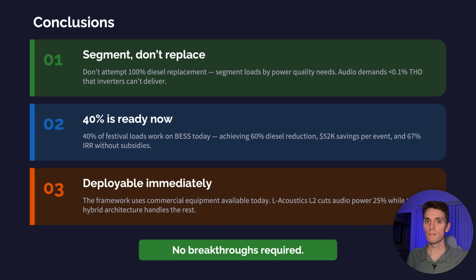3 takeaways. First, segment, don't replace. Don't try to eliminate all the diesel. Audio demands less than 0.1% THD that inverters simply can't deliver. Second, 40% of festival loads work on batteries today, achieving that 60% diesel reduction, $52,000 in savings, and 67% IRR. Third, this framework is deployable immediately with commercial equipment. There's no breakthroughs required.